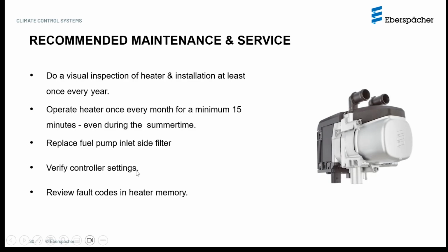Verification of controller settings. This doesn't apply to your application because your controller setting is basically just the push of a button. That's it. So there are no other settings there. And then finally, because we have a much larger capacity for codes, it's always important to review the codes in the ECU. That way you get a true understanding of what kind of issues the heater may have been having, how many hours the unit has operated, and all of that good important stuff. So that is our recommended maintenance and service.